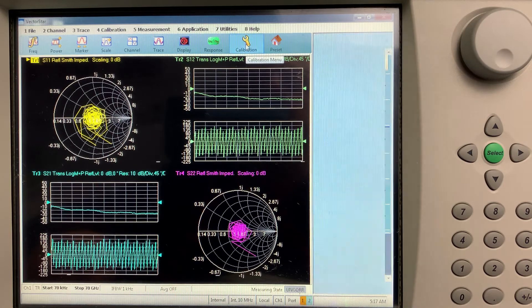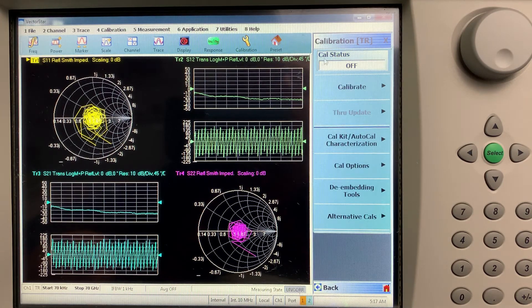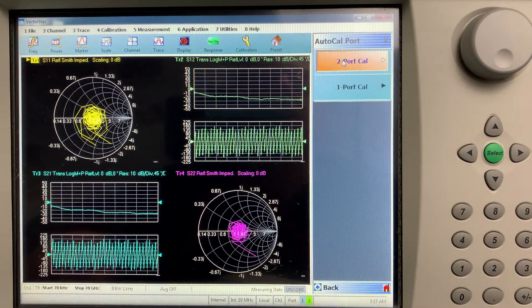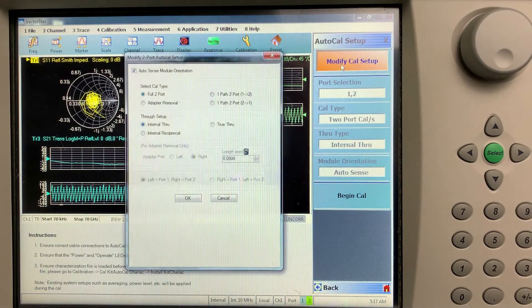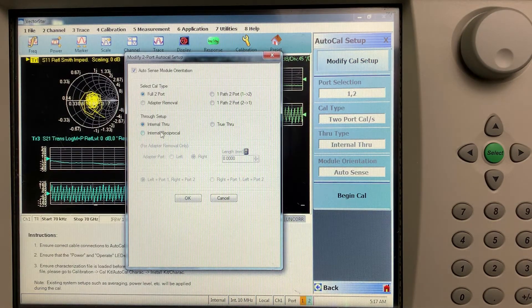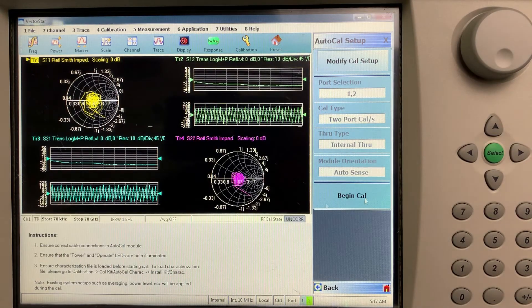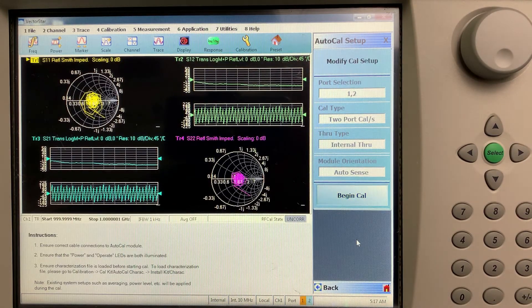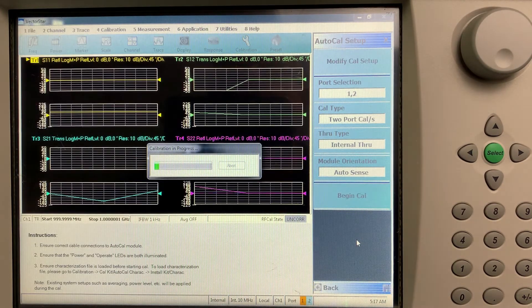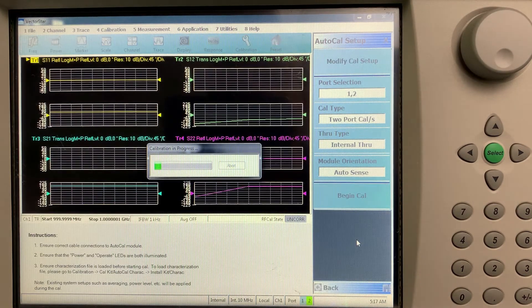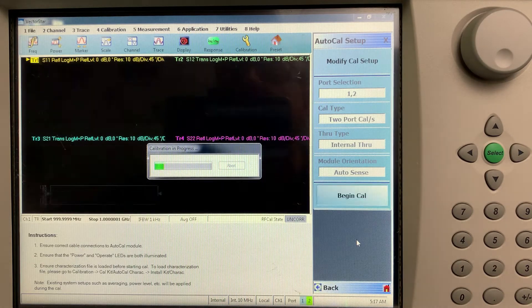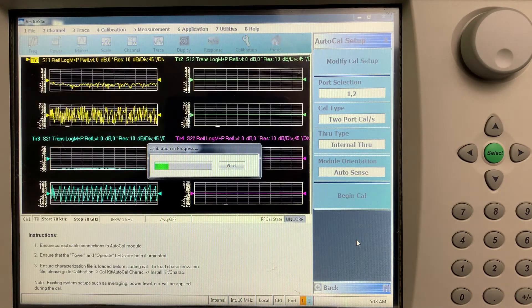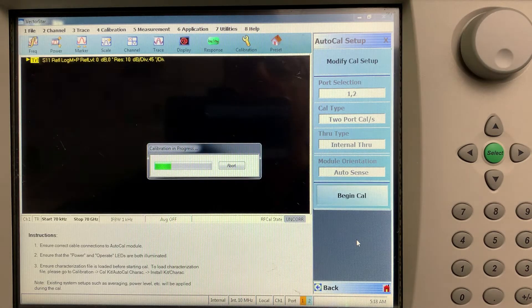So firstly, we go to the calibration menu. We'll calibrate Auto-Cal, 2 port Cal. Do the modified Cal setup. We'll just check and we'll use the internal through. You can use the external through. Check OK and we'll begin Cal. Now what you'll see is a progress bar in the middle of the display as it toggles through its measurements. And you can see the various displays and the traces as it's toggling through.